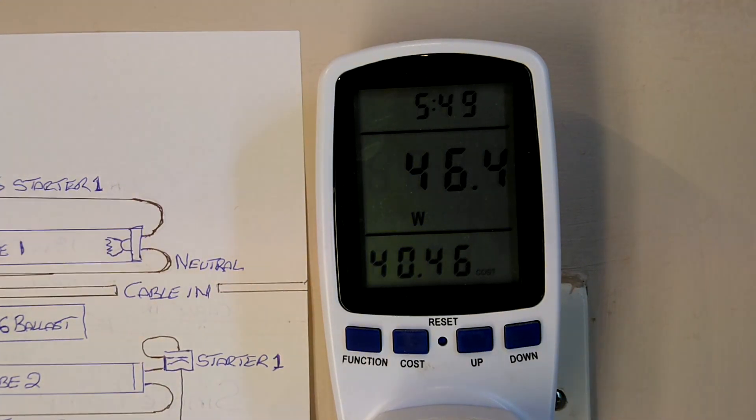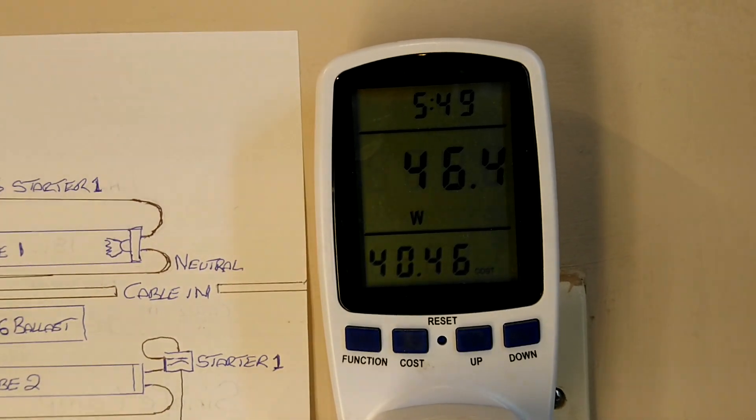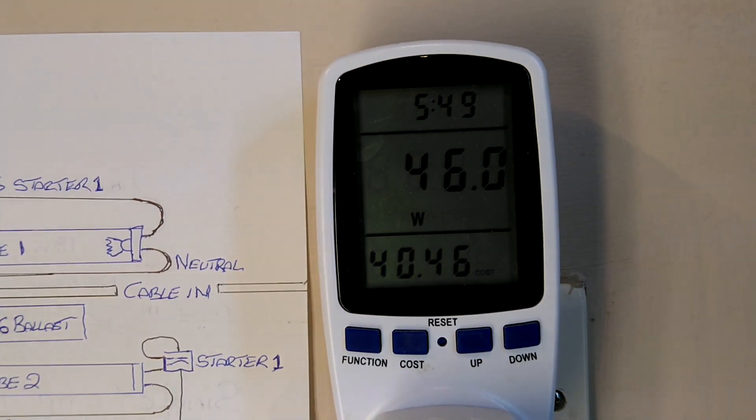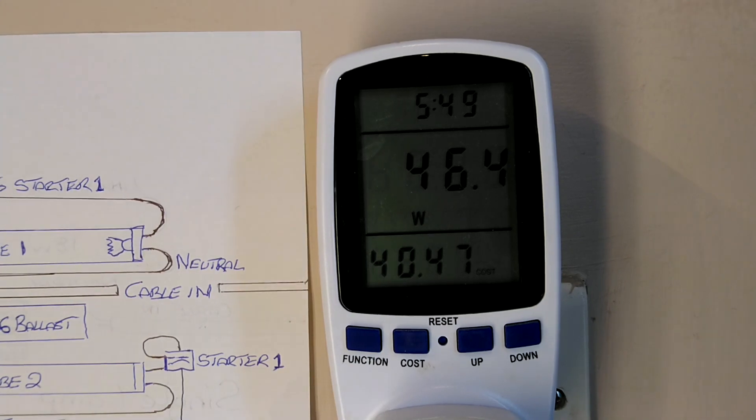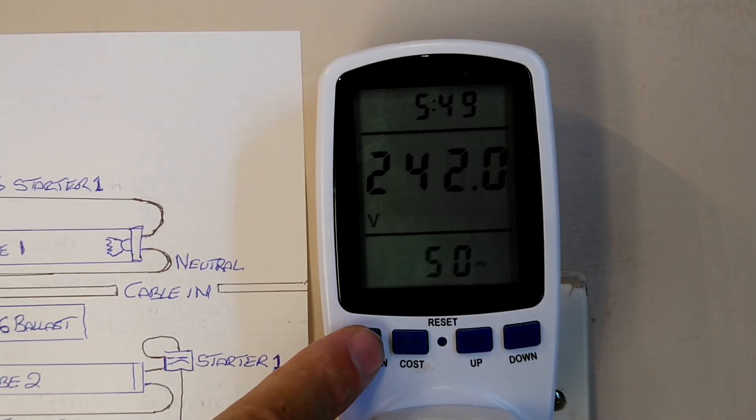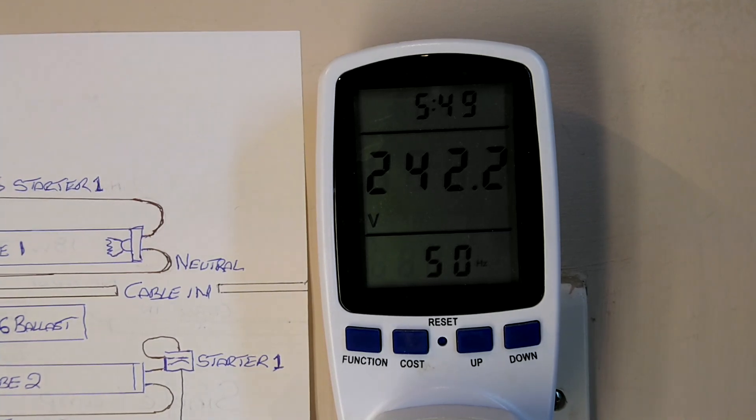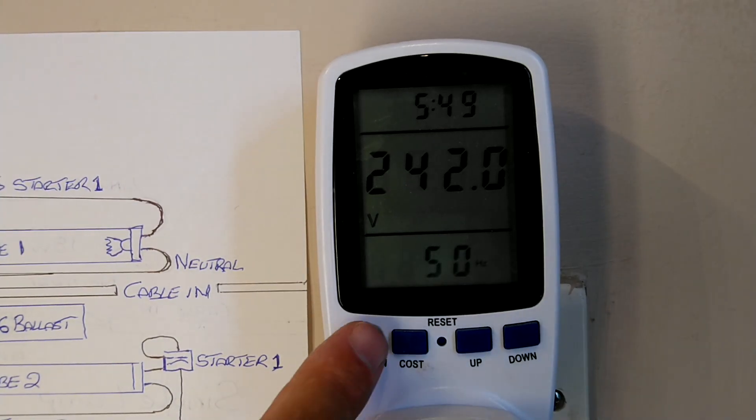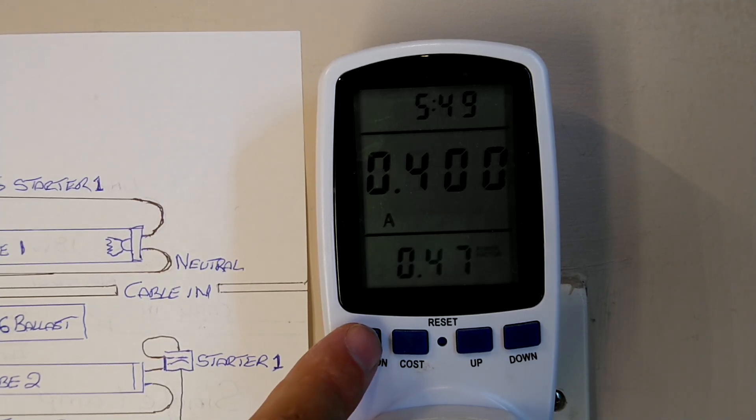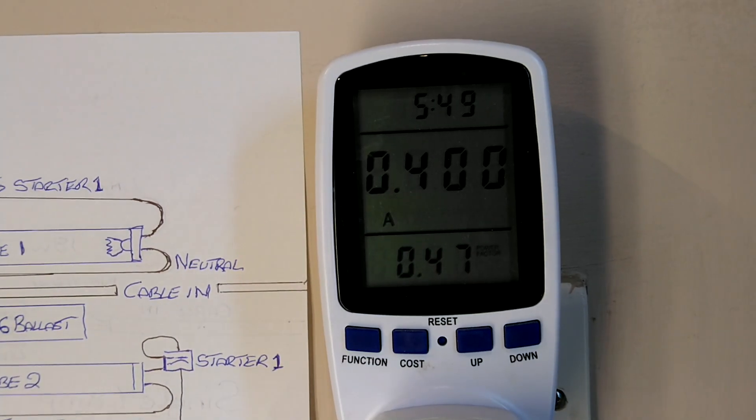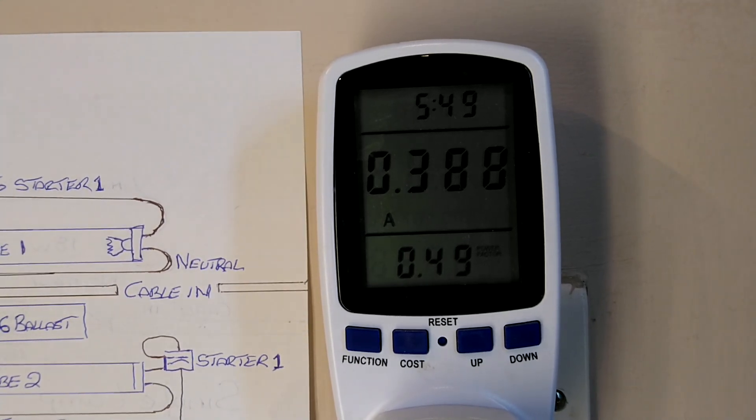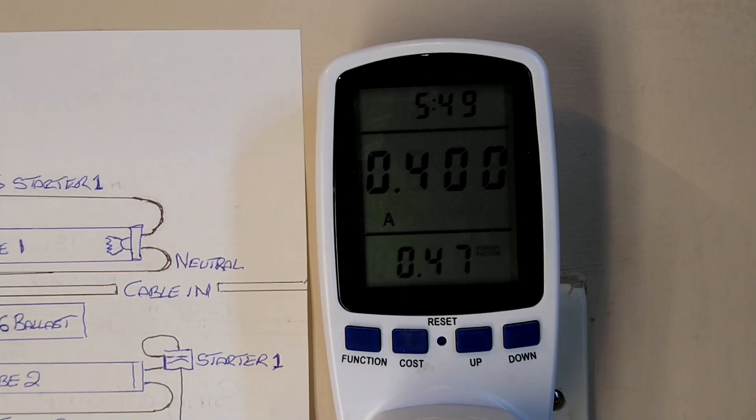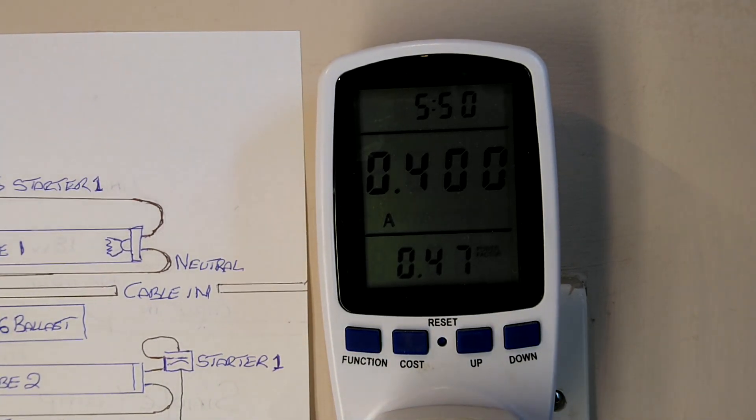Okay, at the moment this twin 36 watt light is currently using 46 watts. Voltage is still 242.0 but it has dropped a little bit from earlier. Amps, it's 0.4 and a power factor of 0.47 to 0.49. So what I think we'll do now is show the insides of the light.